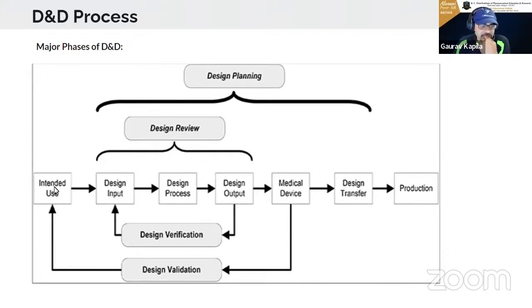First thing is intended use. So intended use is the first thing. Then intended use is broken down into the next phase, which is called the design inputs. Design inputs are further broken down into the design process. So inputs are important for the design or development process to start. And design inputs are related to the intended use. So one subset here is a feed for the other. They are all linked. One step has to be completed before the next starts.